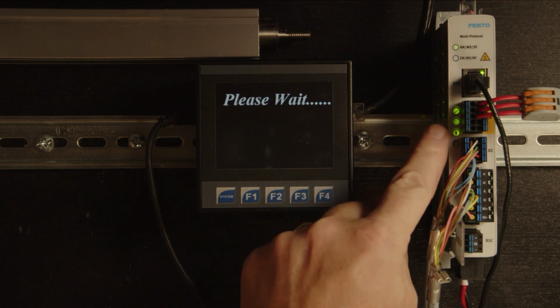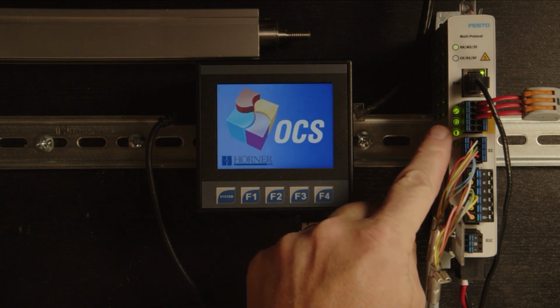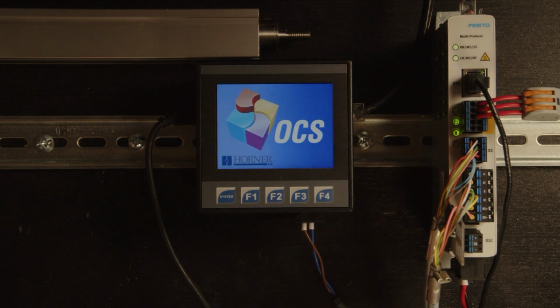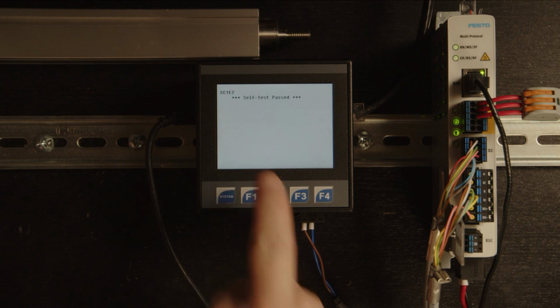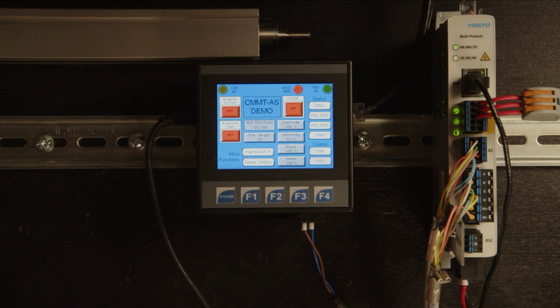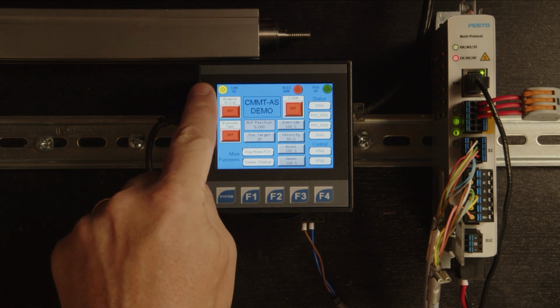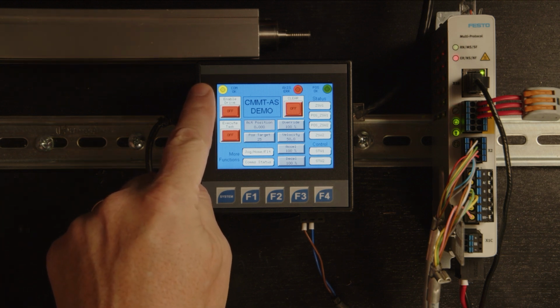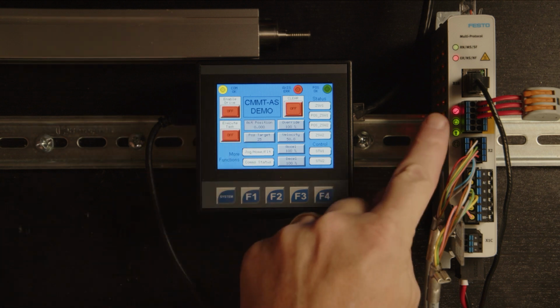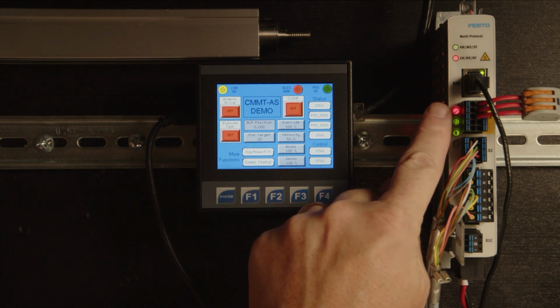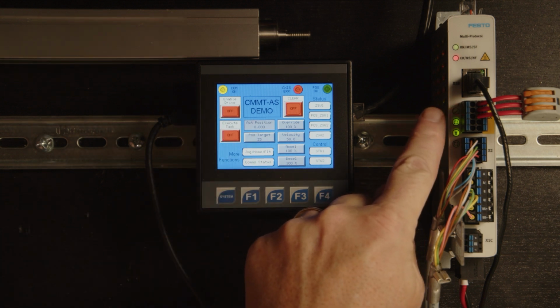You can see the drive LEDs here. Nice large indicators, which is nice. And the OCS is booting up, of course. Okay, so what we're waiting on is a solid comm light, which we have. We also do have an error indication here, so that needs to be cleared before we can proceed.